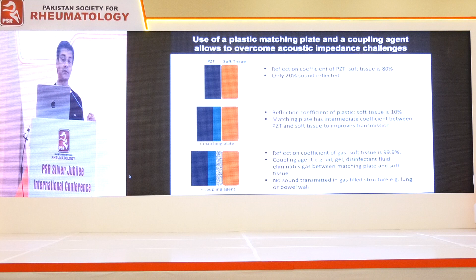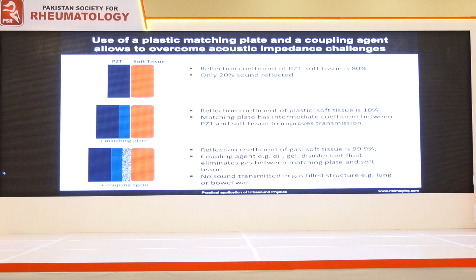So what we do is we actually apply a plastic plate right on top of the disc. Do you remember I talked about that plastic plate on top of the disc? The reason why we apply that is because the reflection coefficient between plastic and soft tissue is 10%. So this means that having a matching plate in between the piezoelectric disc and the soft tissue increases the transmission of sound. And that's why we have that. By contrast, the reason why we have the epoxy resin is because the epoxy resin ensures that the sound waves go directly from the piezoelectric disc and transmit through that epoxy resin.